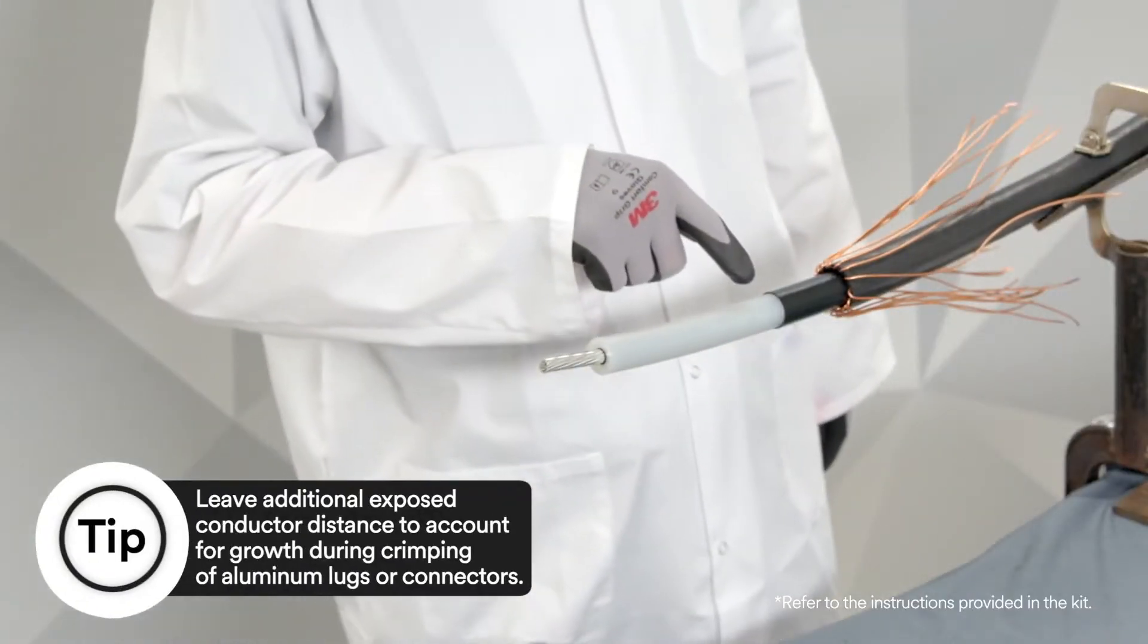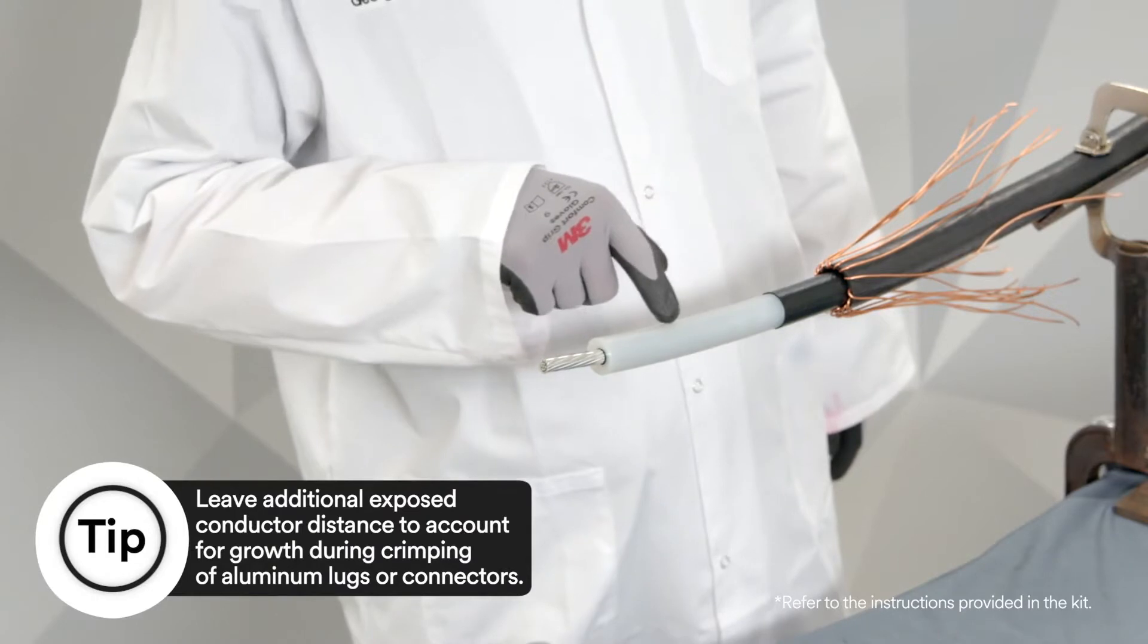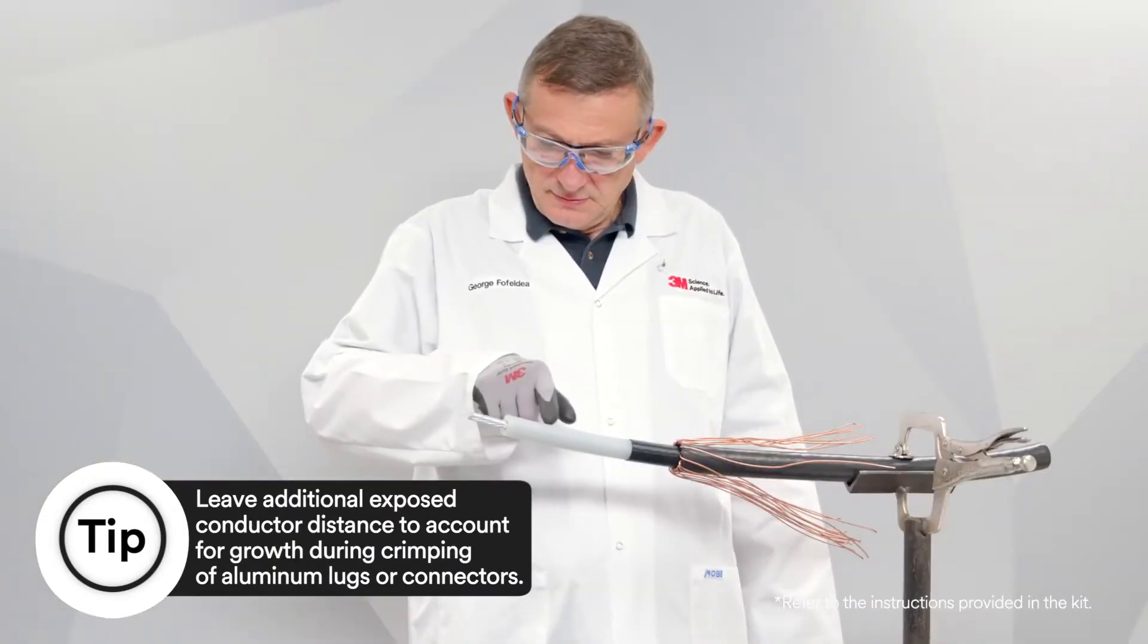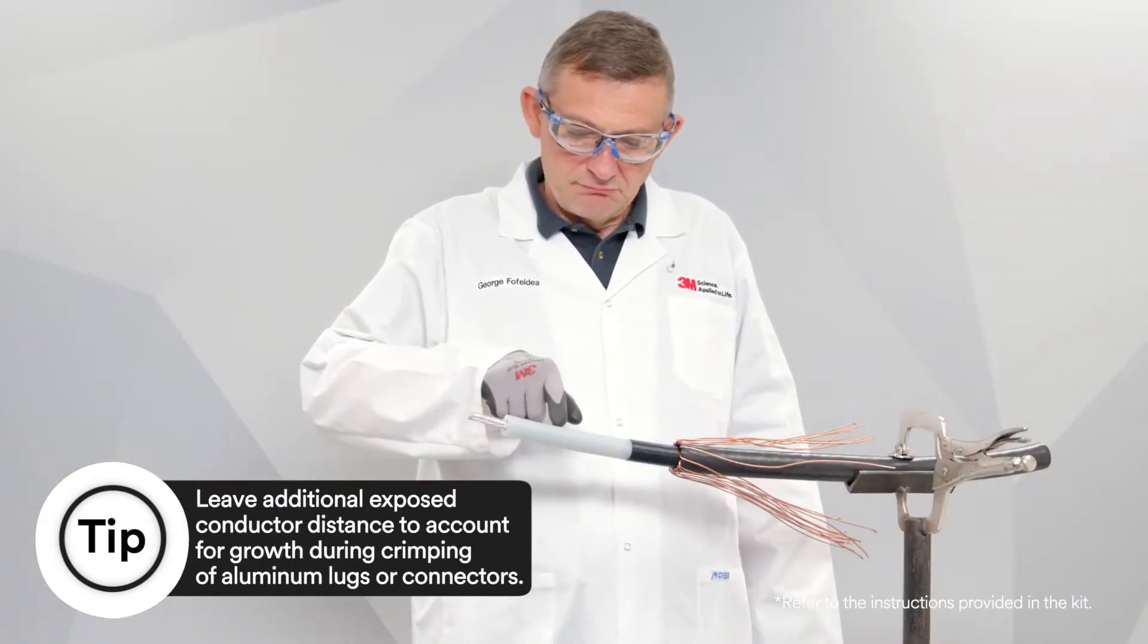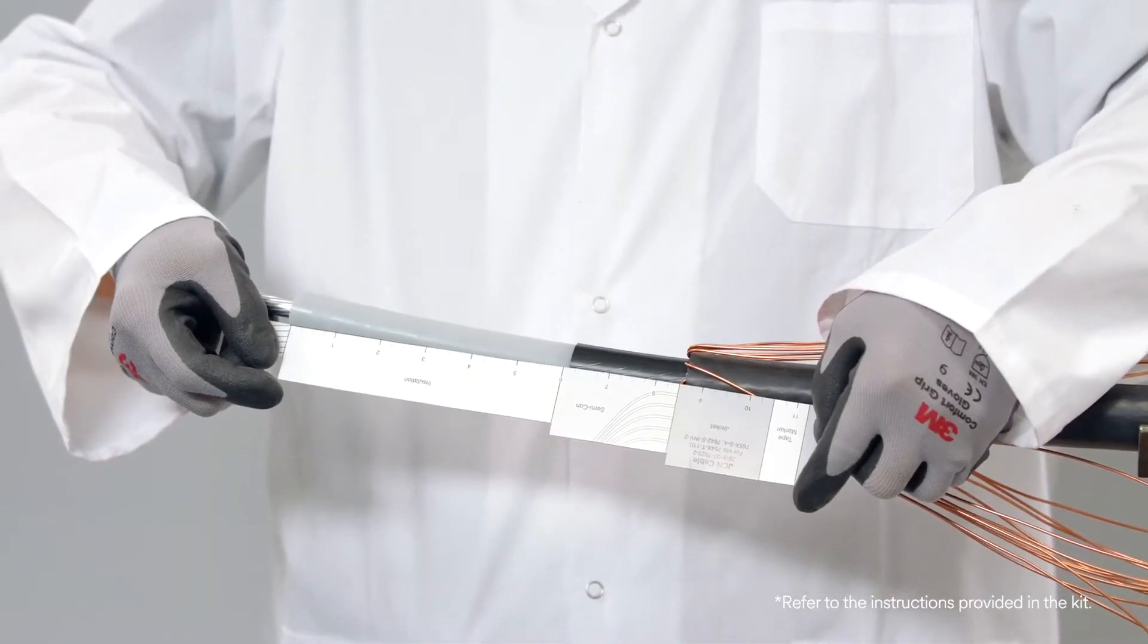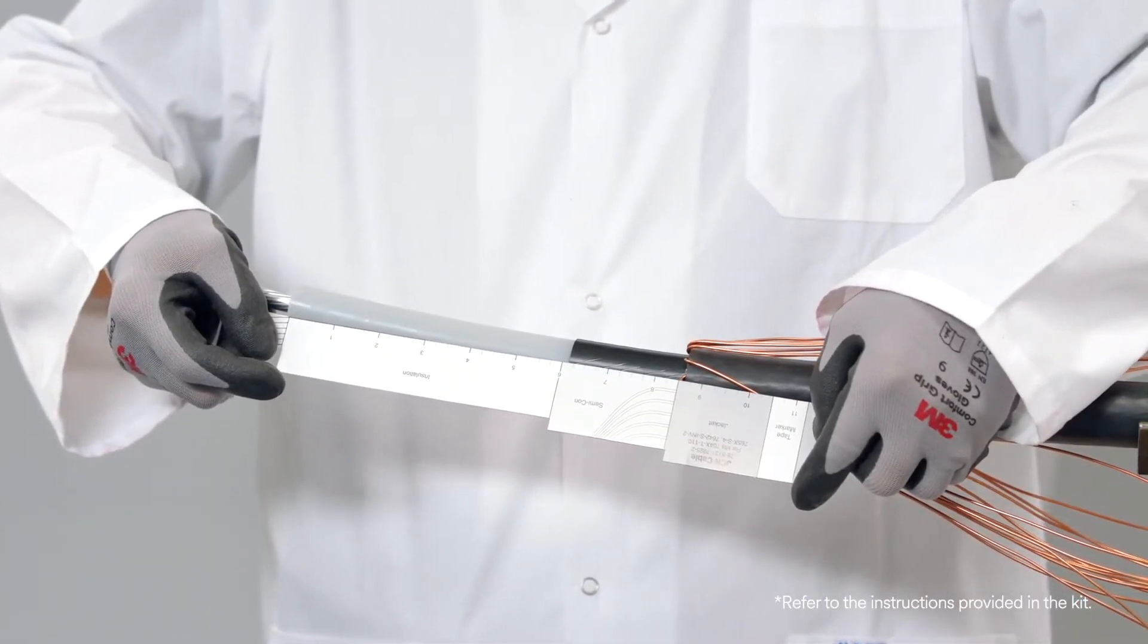It is important to make sure that you've removed all remnants of the Semi-Con layer, even if the Semi-Con layer comes off as one layer. You don't want to have any remaining black areas or particles on the cable insulation layer.